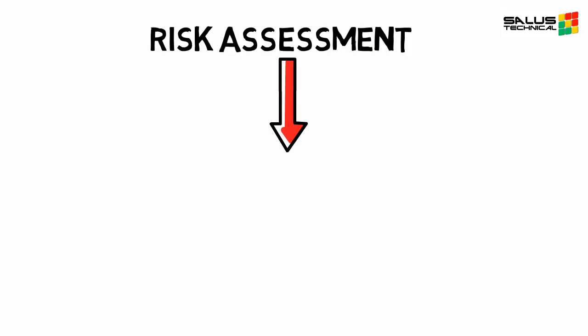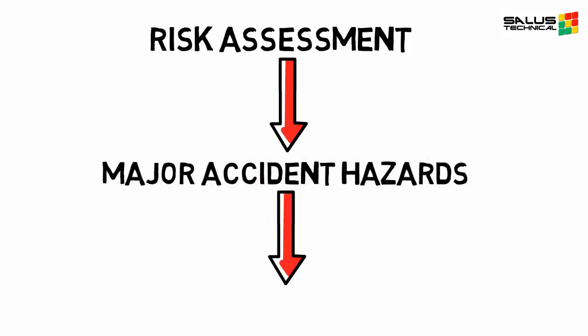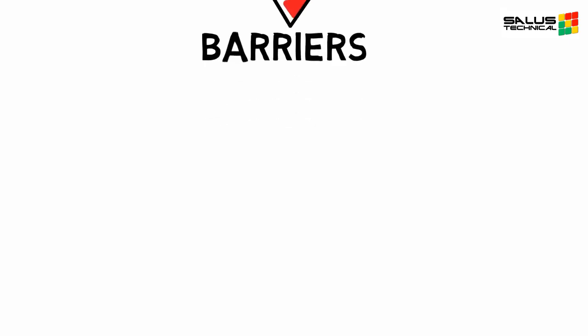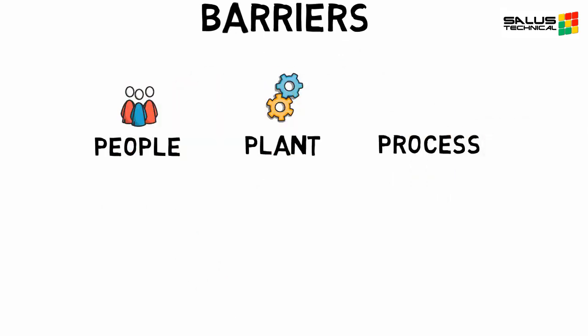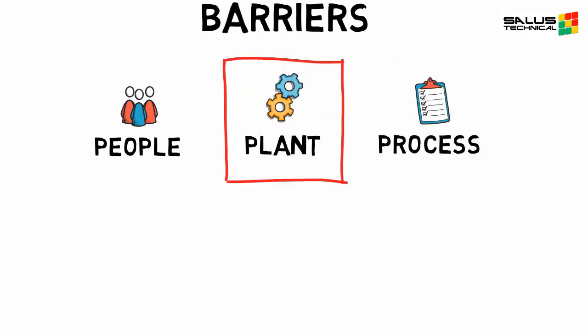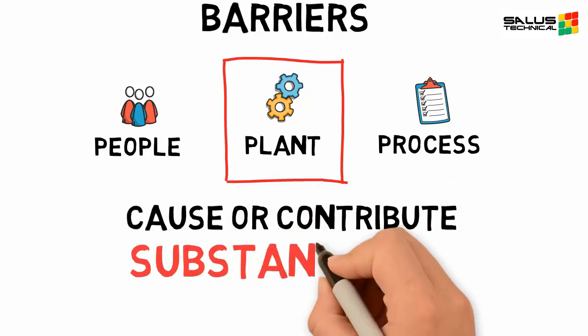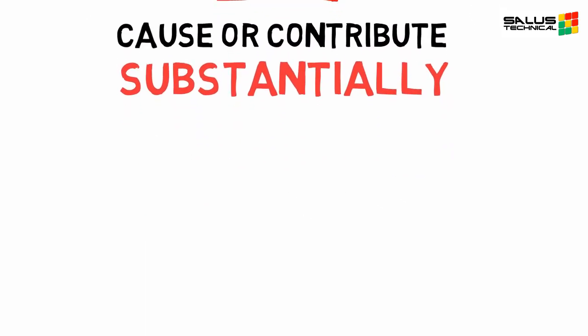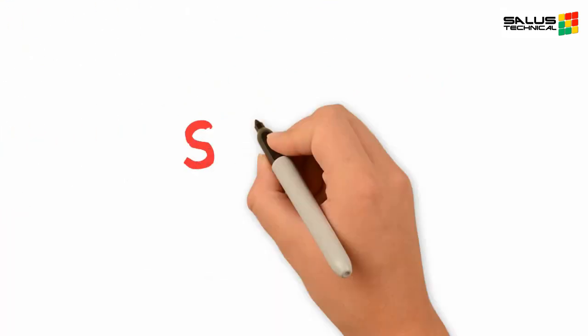In our risk assessments, we identify our major accidents and the barriers in place to prevent, control or mitigate them. These can be categorised as people, plant or process. Plant barriers are the physical equipment, including software, that we have on our installations. If a plant barrier's failure could cause or contribute substantially to a major accident, it is classified as a safety and environmental critical element, or a SECE.